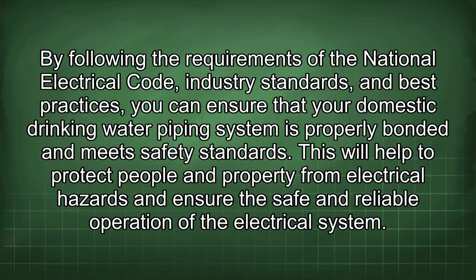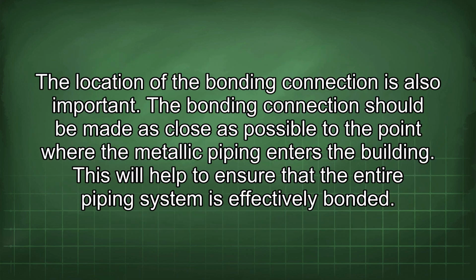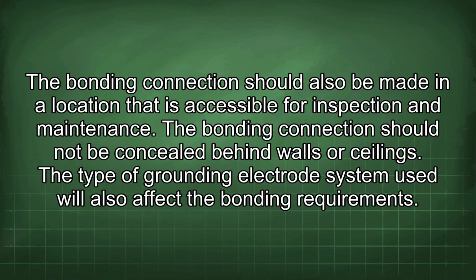The location of the bonding connection is also important. The bonding connection should be made as close as possible to the point where the metallic piping enters the building. This will help to ensure that the entire piping system is effectively bonded. The bonding connection should also be made in a location that is accessible for inspection and maintenance. The bonding connection should not be concealed behind walls or ceilings.